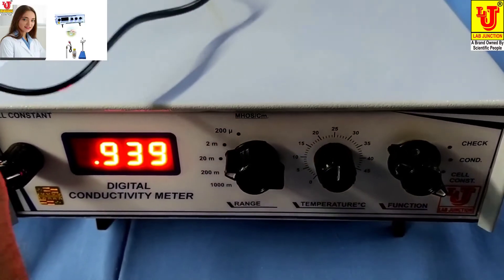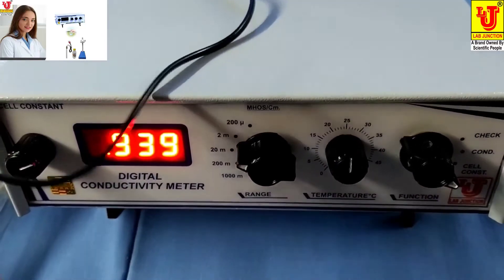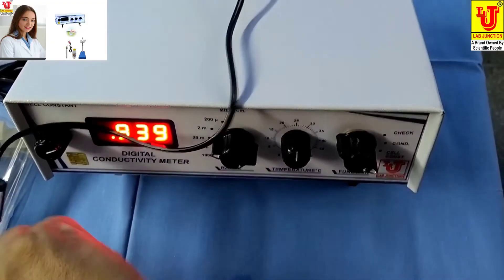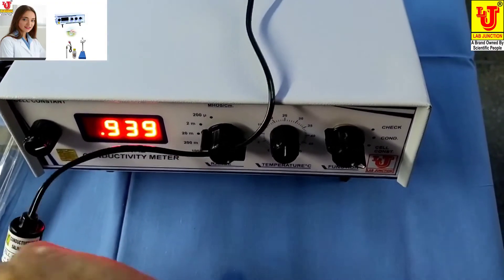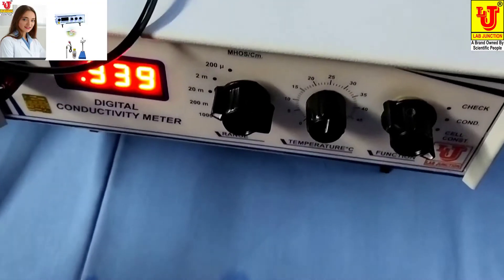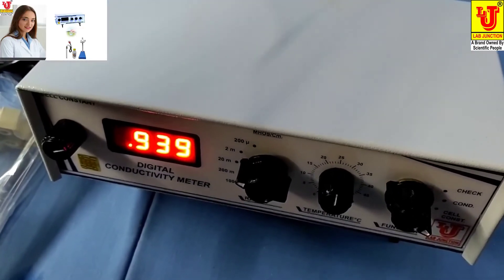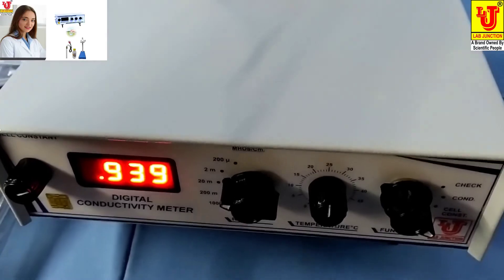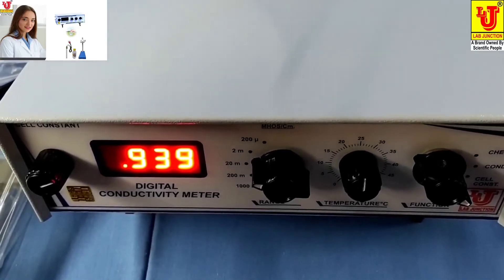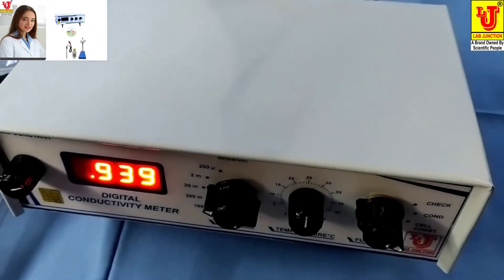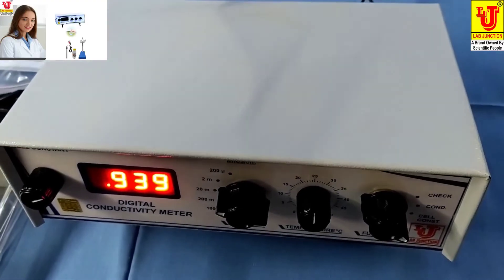Now suppose you leave your premises and come back after a week. You need to work again, but you don't have the conductivity solution. How can you calibrate?